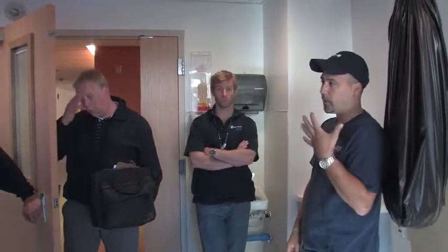If you lose the transformer, we built the panels so that you have a spare transformer right next to the other transformer. So if you come in here and find the transformer's blown, all you have to do is lift a wire and move it over, and you're back up and running. Then you just pull that old one out and replace it. So there's no need to run and try to find one. It's already set up there with you. And there are inline fuses in there.